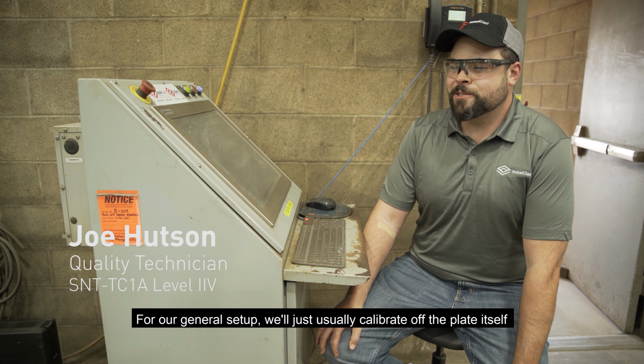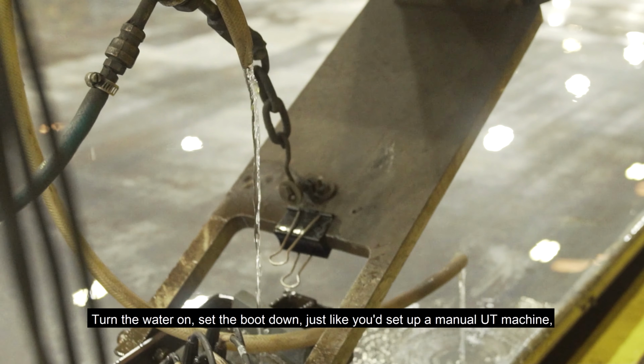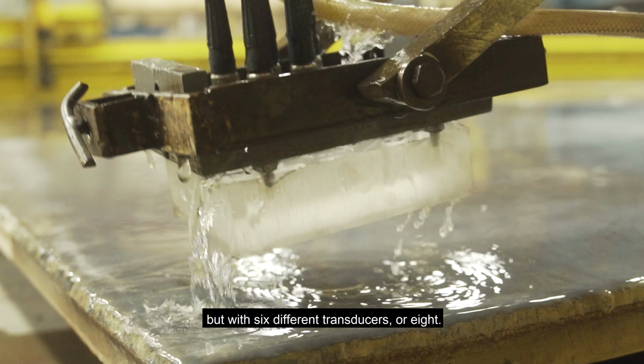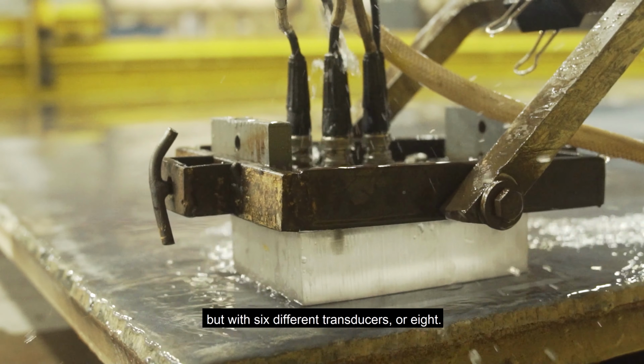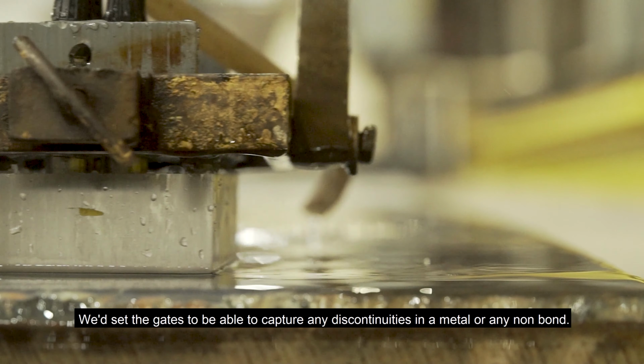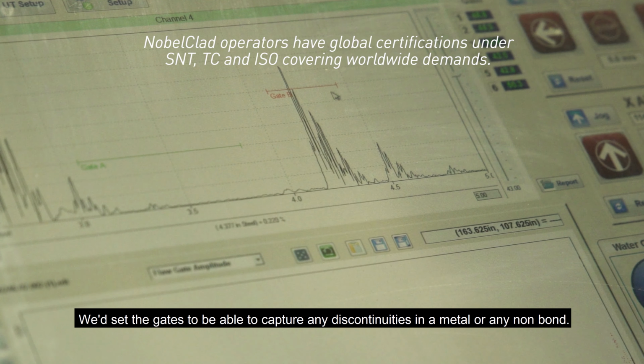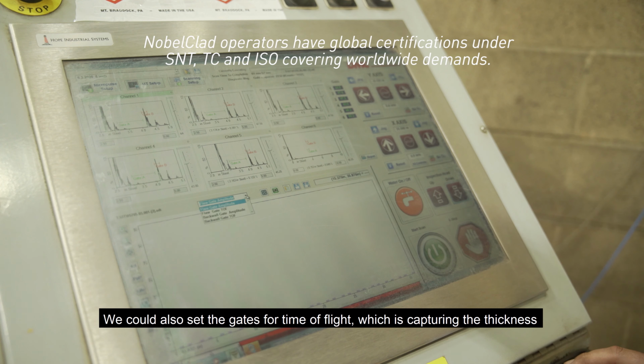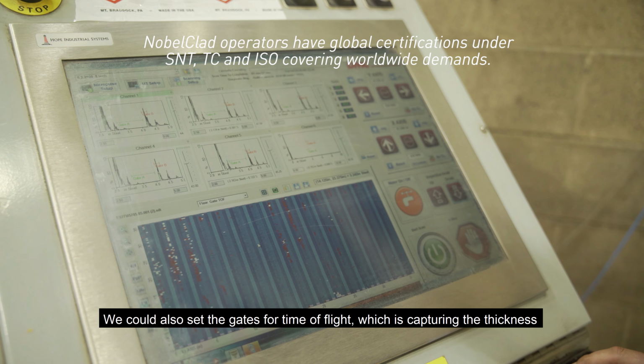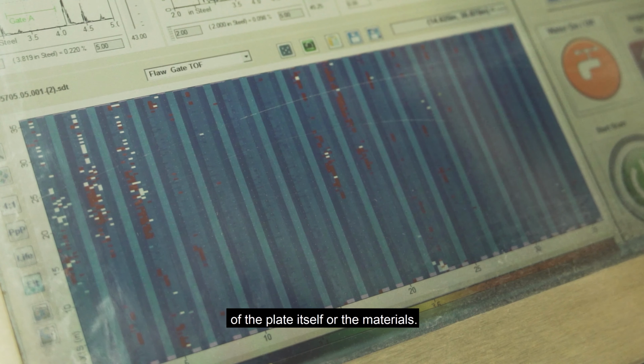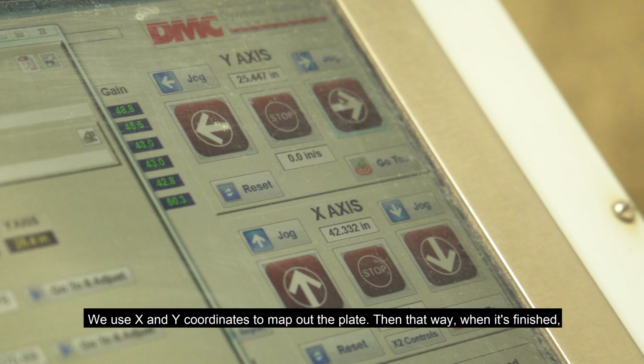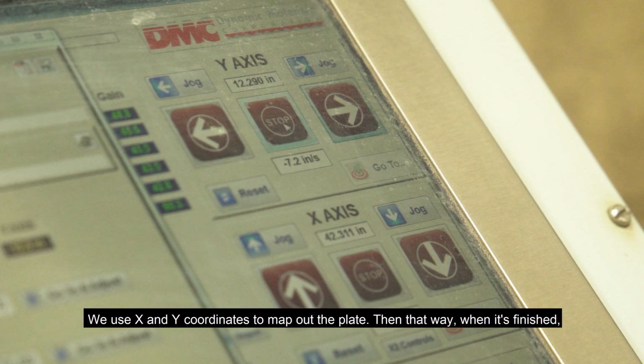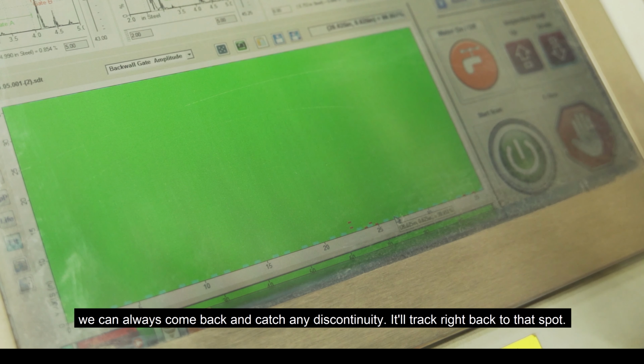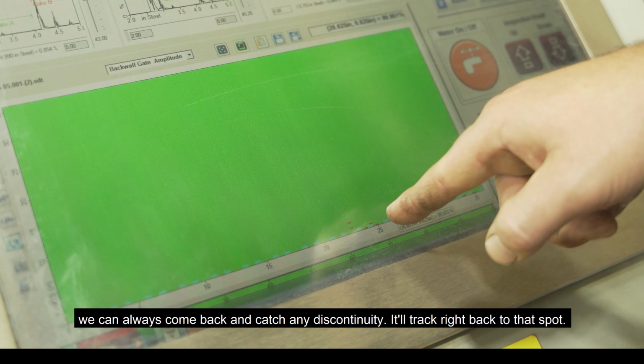For our general setup, we'll usually calibrate off the plate itself, unless specified by a customer, and use a calibration block. Turn the water on, set the boot down, just like you'd set up a manual UT machine, but with 6 different transducers or 8. And we'd set the gates to be able to capture any discontinuities in the metal or any non-bond. We could also set the gates for time of flight, which is capturing the thickness of the plate itself or the materials. We use X and Y coordinates to map out the plate, and then that way when it's finished, we can always come back and catch any discontinuity. It'll track right back to that spot.